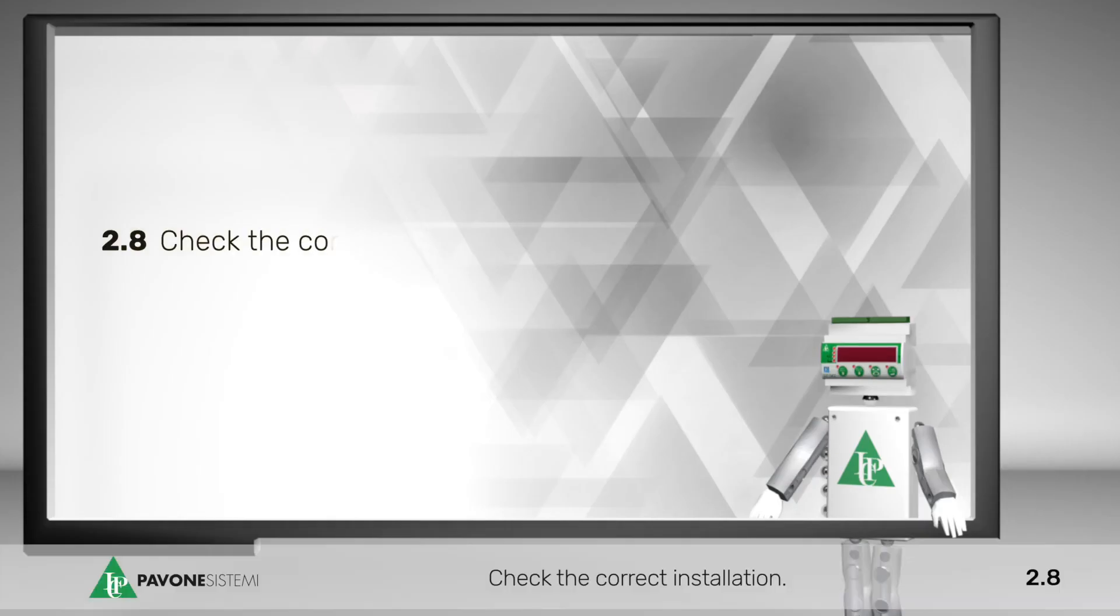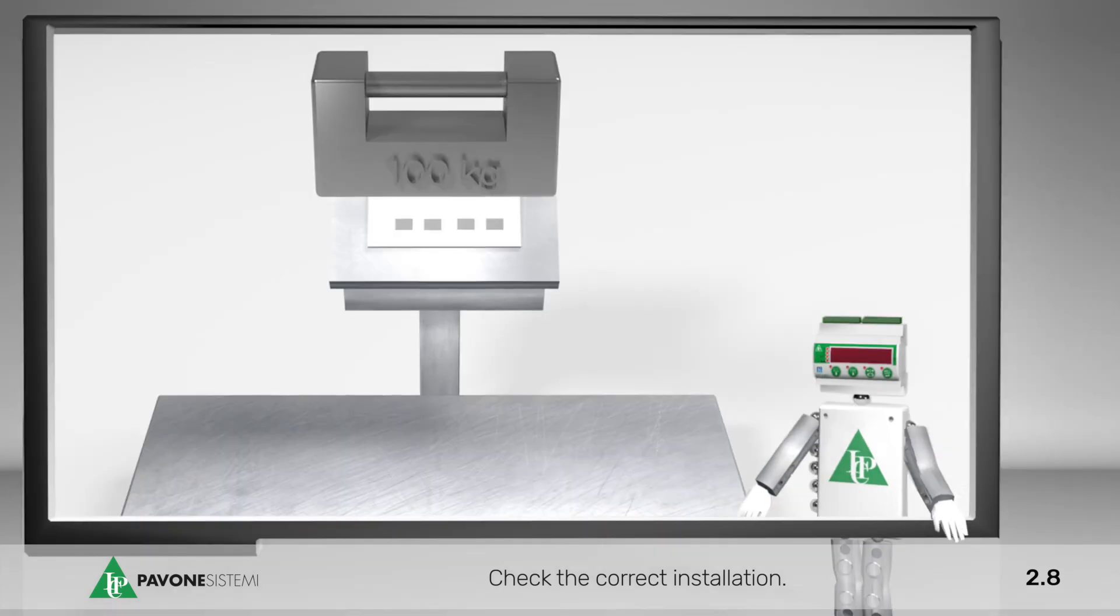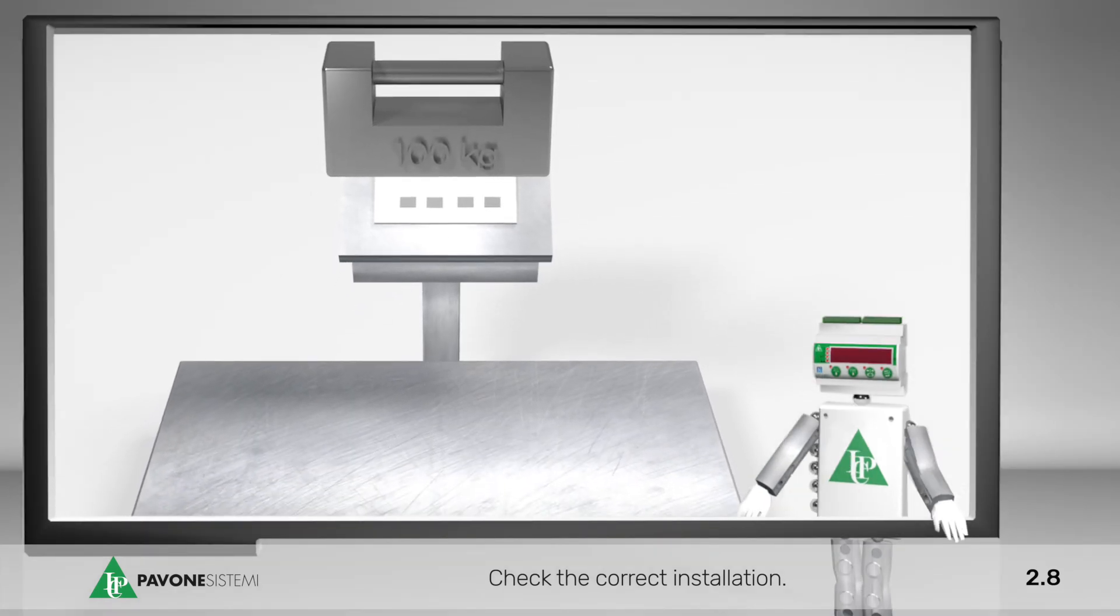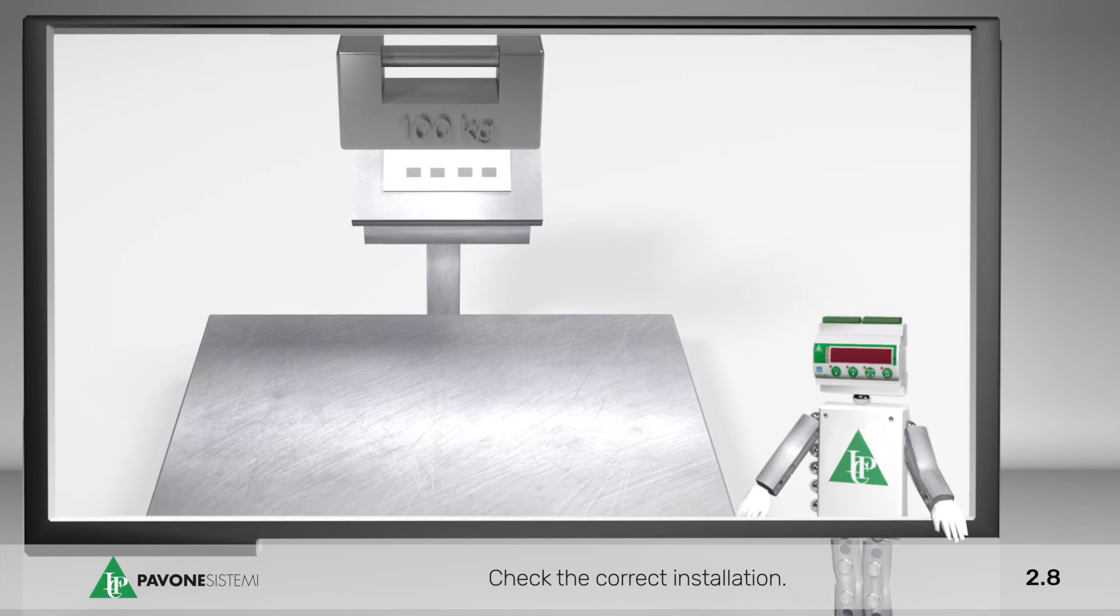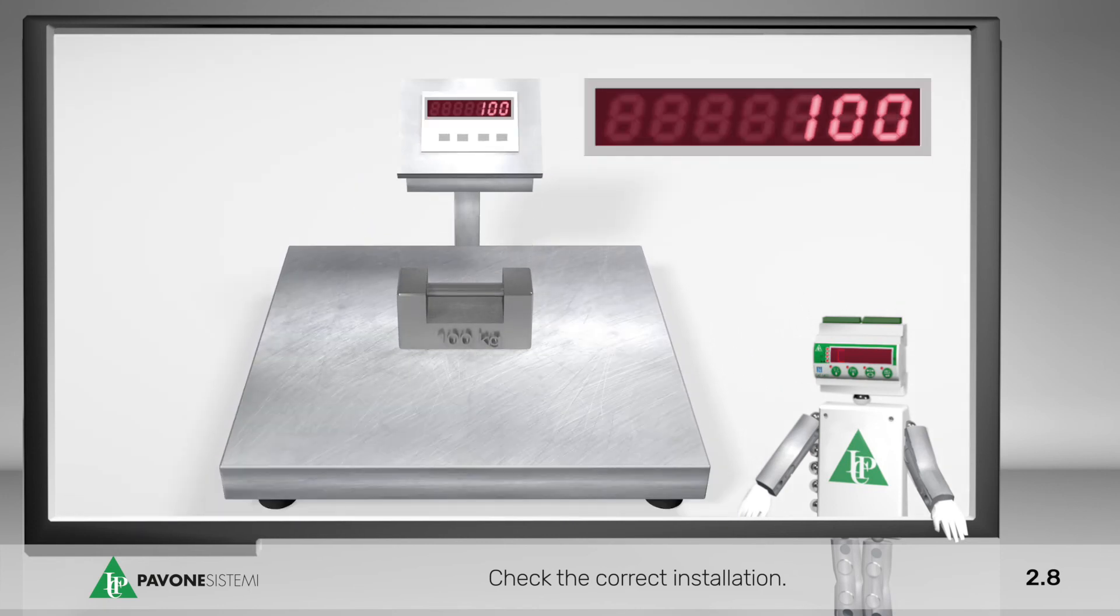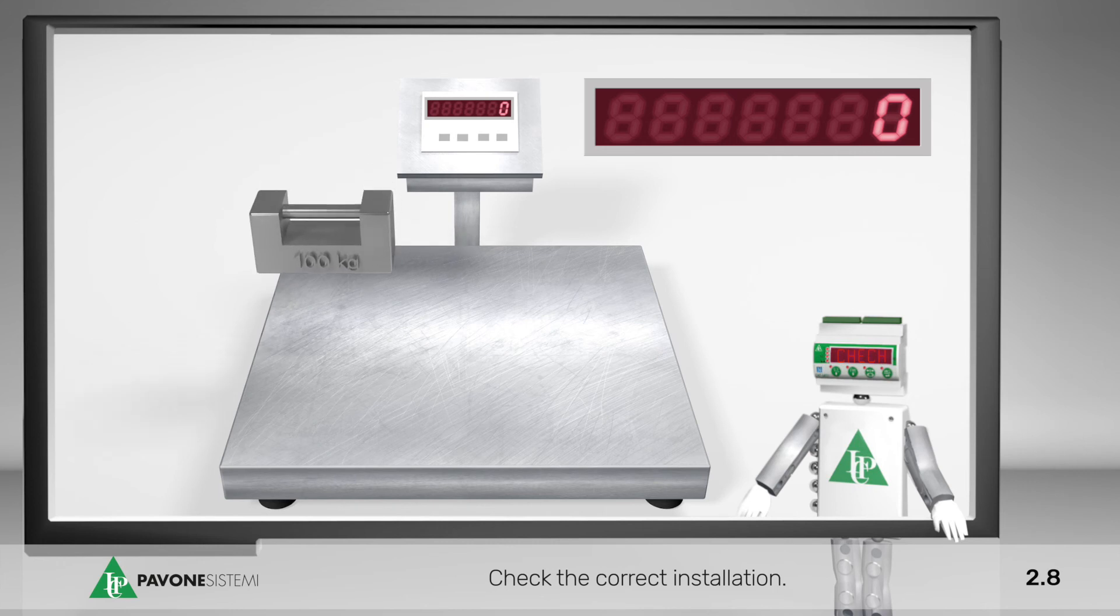Check the correct installation. To verify the correct mechanical installation and the effectiveness of the weighing system, perform the following tests, carrying out a zeroing of the weighing indicator of the load cell. Apply a known load to the center and then to all the corners.